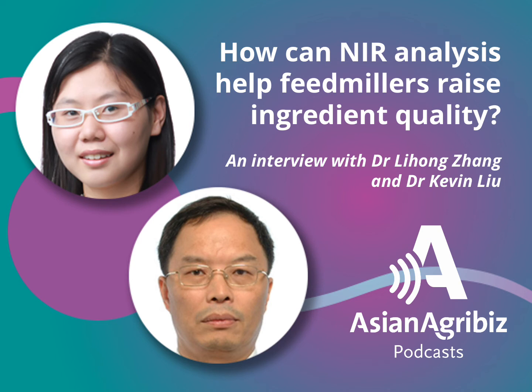In addition, we offer prediction for proximate for layer, broiler, and swine feeds when their formulations are consistent. Users must take caution on finished feed calibrations, as changes in formulations will lead to reduced prediction accuracy. For example, if a calibration set is based on corn soybean meal-based diets, we cannot apply it to wheat soybean meal-based diets. In such a case, new analytical data are required to enrich the existing NIR calibration. Therefore, recalibration is required whenever new ingredients are used in formulation.